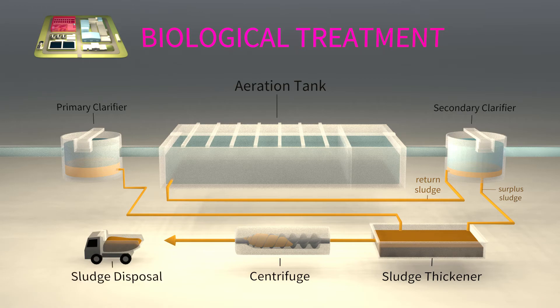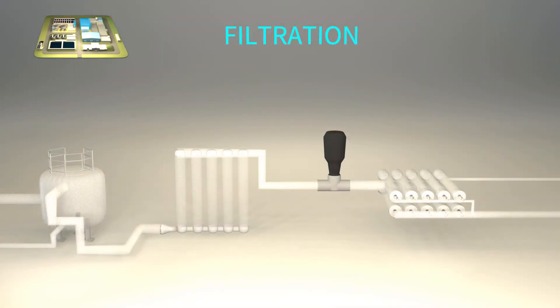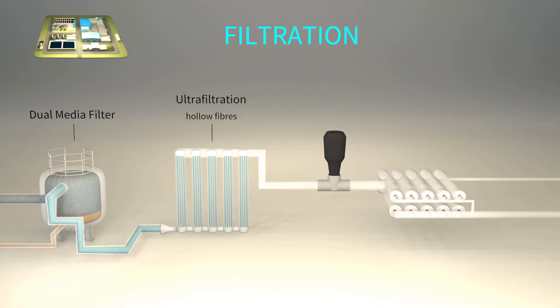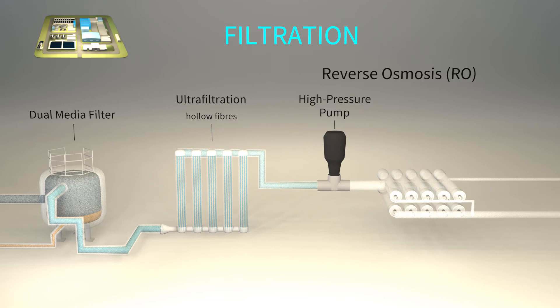In the subsequent filtration, the water is purified by a set of finer and final filters. Dual media filters followed by ultrafiltration remove suspended solids. In a multi-step reverse osmosis, high-pressure pumps press water through a membrane to remove even dissolved ions, like salt. The water passing the membrane is pure for reuse. In the reject not passing the membrane, salt concentrates.